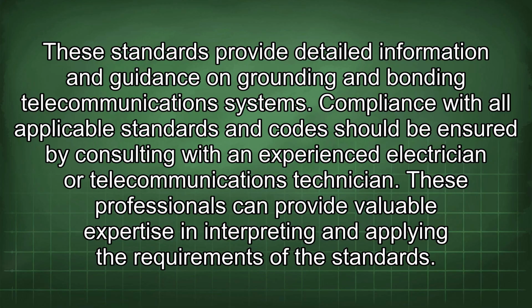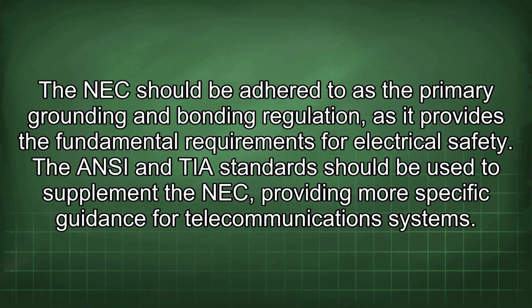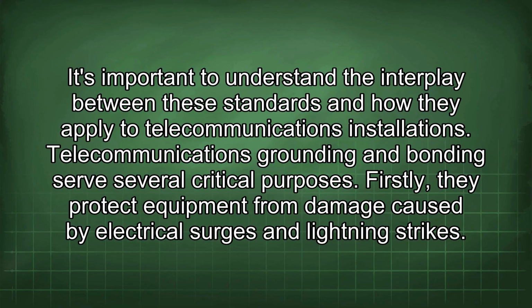Compliance with all applicable standards and codes should be ensured by consulting with an experienced electrician or telecommunications technician. These professionals can provide valuable expertise in interpreting and applying the requirements of the standards. The NEC should be adhered to as the primary grounding and bonding regulation, as it provides the fundamental requirements for electrical safety. The ANSI and TIA standards should be used to supplement the NEC, providing more specific guidance for telecommunications systems. It's important to understand the interplay between these standards and how they apply to telecommunications installations.